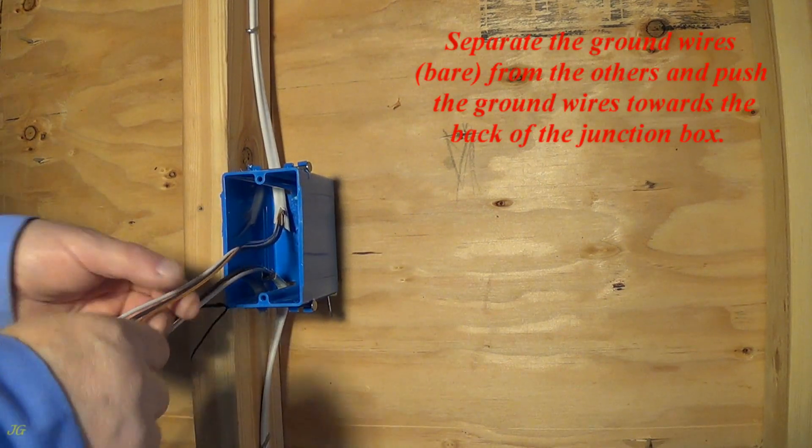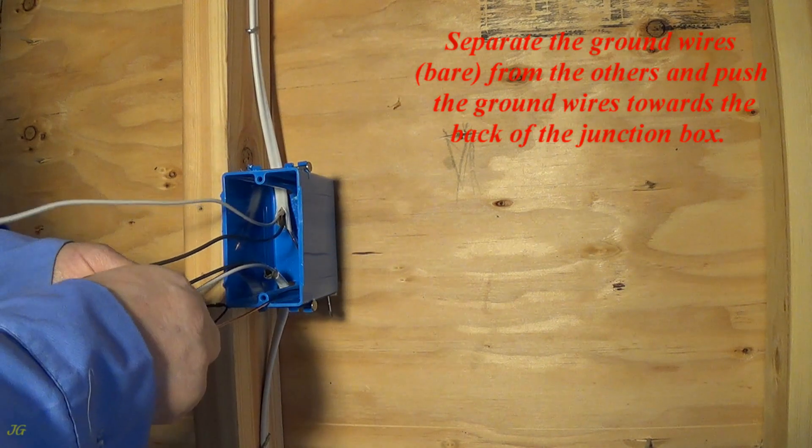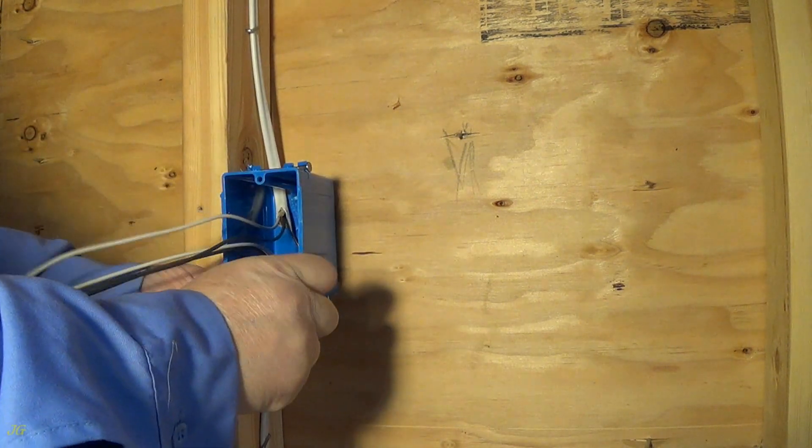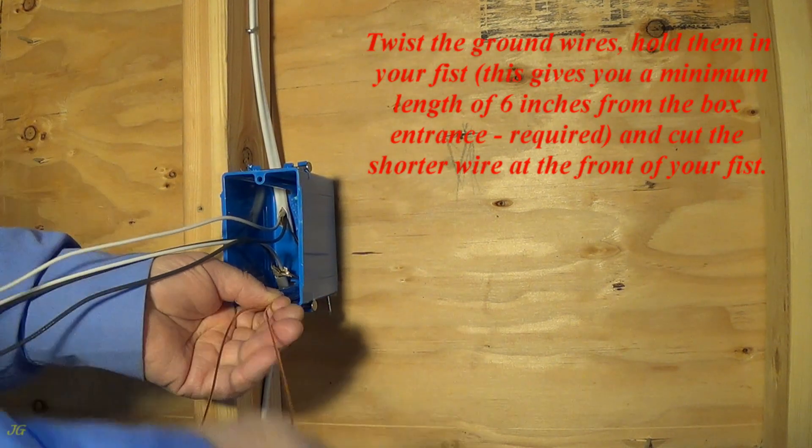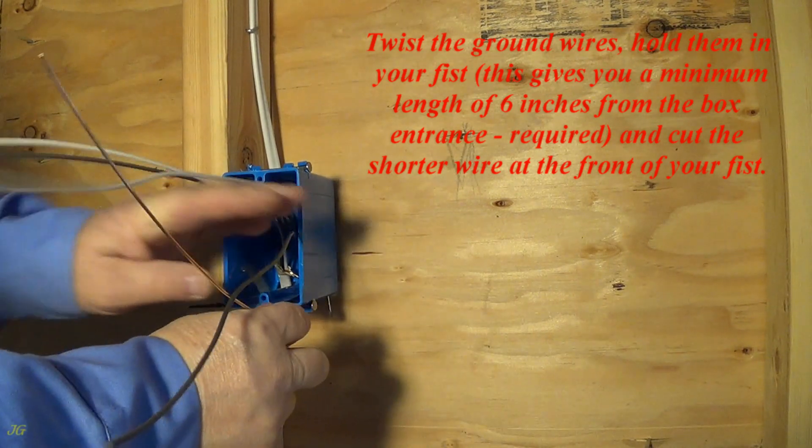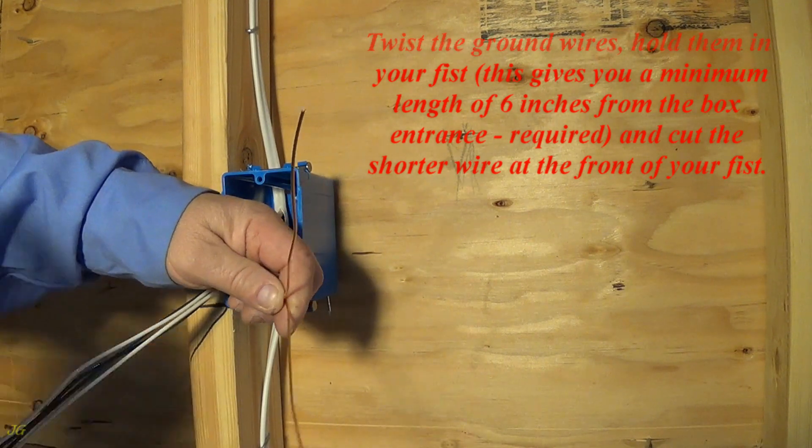Separate the ground wires, bare, from the others and push the ground wires towards the back of the junction box. Twist the ground wires, hold them in your fist. This gives you a minimum length of 6 inches from the box entrance, required, and cut the shorter wire at the front of your fist.